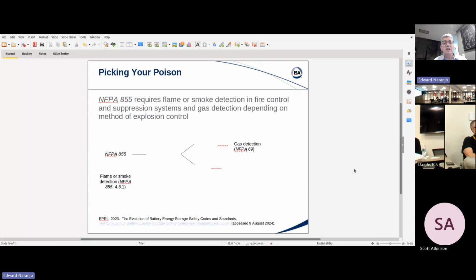And if you're using fire protection or active fire protection as your method of prevention or mitigation, then gas detection is required. On the other hand, and that's NFPA 68, if you must have or you choose to have a passive method of protection, then your system must be equipped with some sort of venting. So you don't have a choice. You either have venting built into your container in order to prevent explosions, or you're using active fire protection and gas detection is required. So it's either or, and both are perfectly acceptable under NFPA 855.